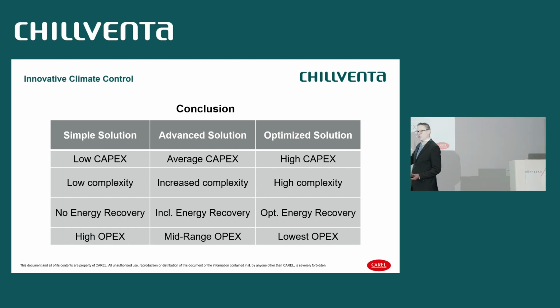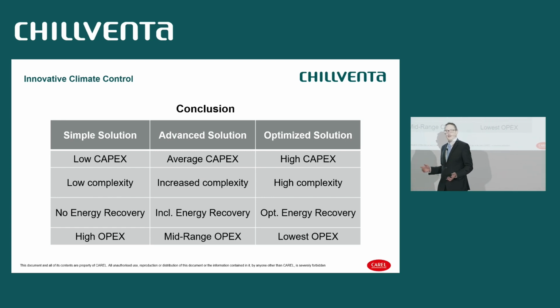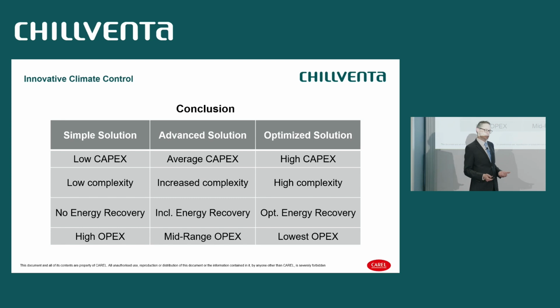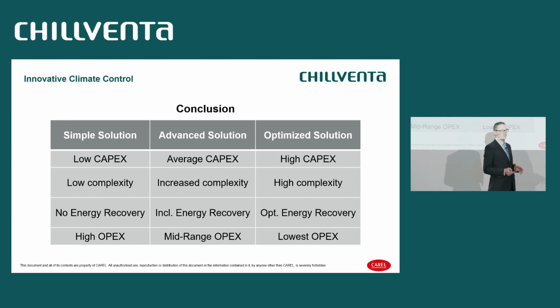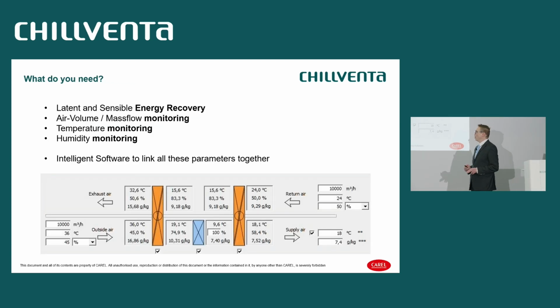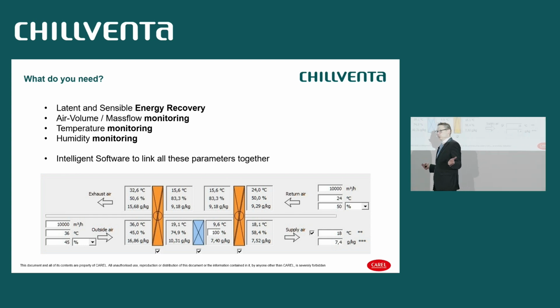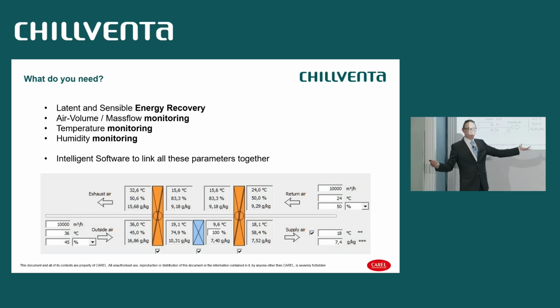An air handling unit on the roof, nobody sees it. It's a black box. So you don't think about it. But it is worth thinking about clever systems, rotating heat exchangers, highest efficiencies, the least amount of space needed during installation, the least amount of auxiliary energy needed to make them run, and pair it with controls. So what you need for it is very simple. What do we need to make that system operate? We need two rotors, sensors, and a control logic.